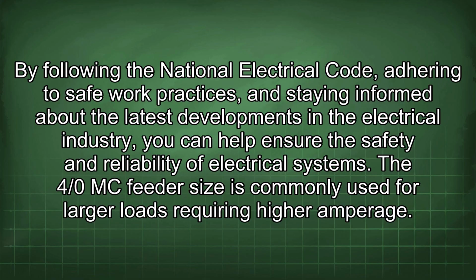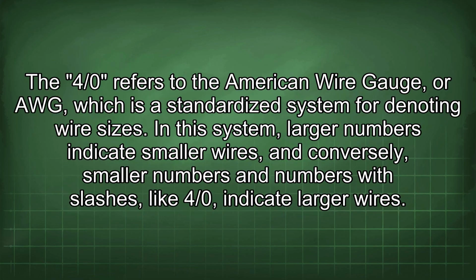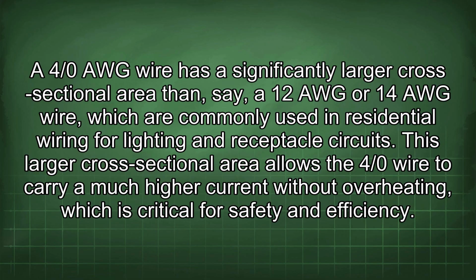The 4/0 MC feeder size is commonly used for larger loads requiring higher amperage. The 4/0 refers to the American wire gauge, or AWG, which is a standardized system for denoting wire sizes. In this system, larger numbers indicate smaller wires, and conversely, smaller numbers and numbers with slashes, like 4/0, indicate larger wires. A 4/0 AWG wire has a significantly larger cross-sectional area than, say, a 12 AWG or 14 AWG wire, which are commonly used in residential wiring for lighting and receptacle circuits.